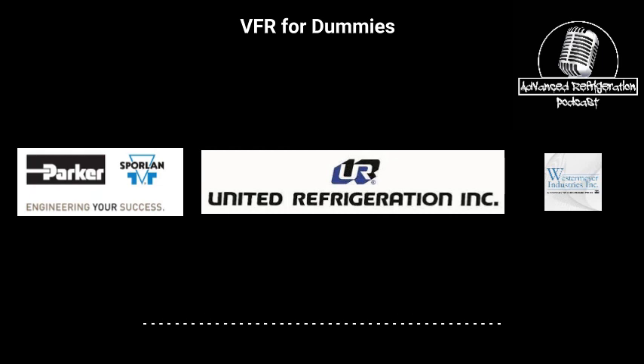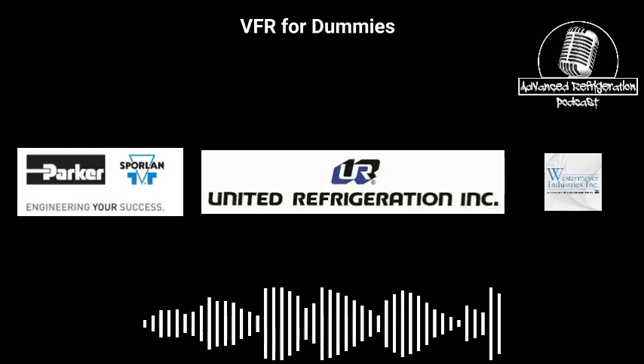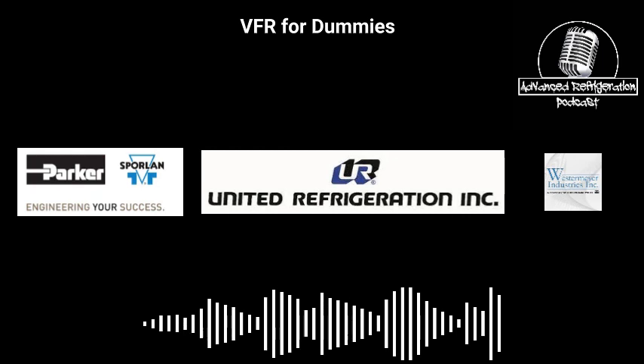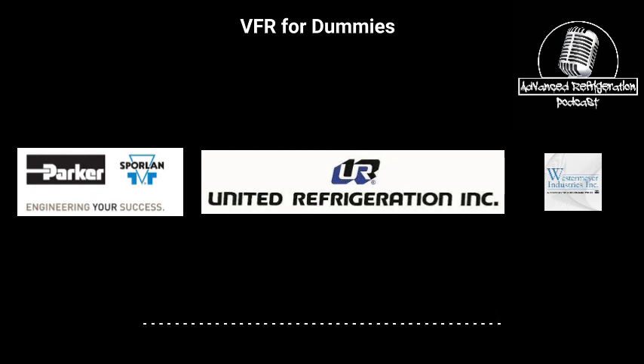All right, so, can you say it? Yes, sir. This is a pretty basic line diagram of a 2-compressor heat recovery system. Starting from left to right, we have a suction pipe that comes in and hits the accumulator to the compressors. Gotcha. High pressure, low pressure. This is that third pipe I was talking about that can be discharge or secondary suction. Okay. Liquid is always liquid, it just depends on which way it's flowing. Okay.